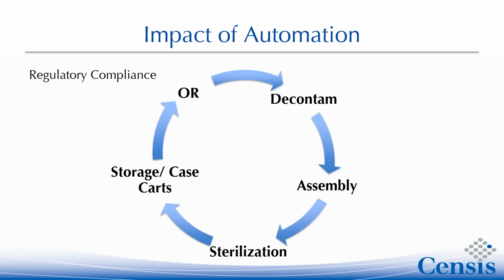We already mentioned a few examples, like the system producing reminders that alert staff that when sterilizing a tray that includes an implant, the sterilizer load needs to have a biological indicator test on board. So it gives them an audible and visual alert saying don't forget to add the biological test.